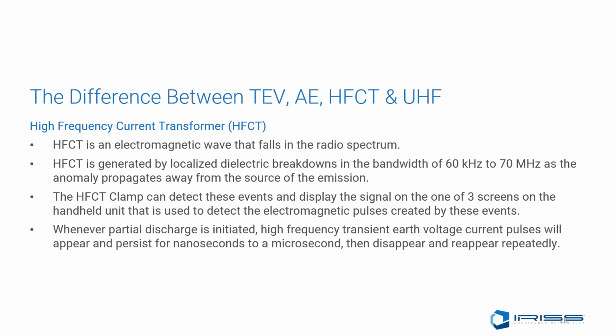The difference between HFCT, TEV, AE, and UHF. HFCT stands for High Frequency Current Transformer. HFCT is an electromagnetic wave that falls in the radio spectrum. It is generated by localized dielectric breakdowns in a bandwidth of 60 kHz to 70 MHz as the anomaly propagates away from the source of the emission.